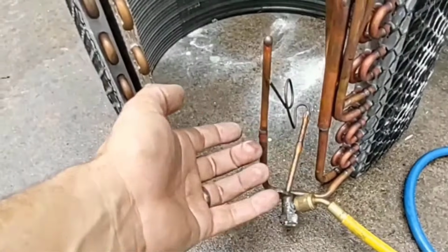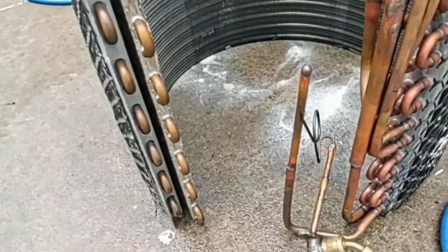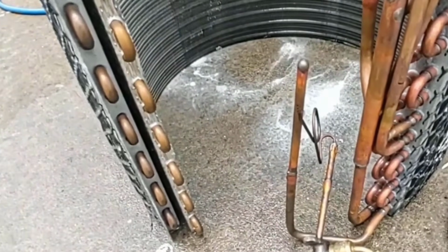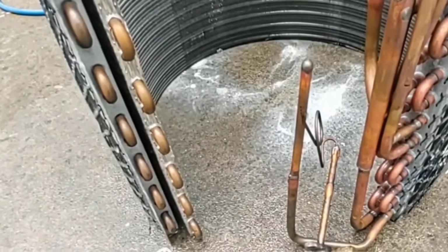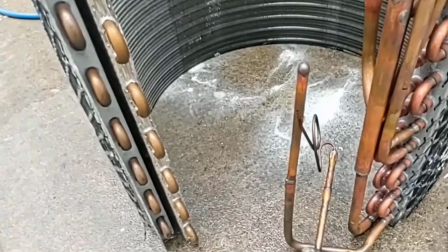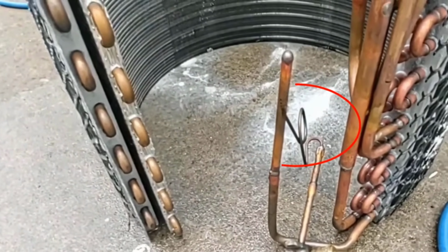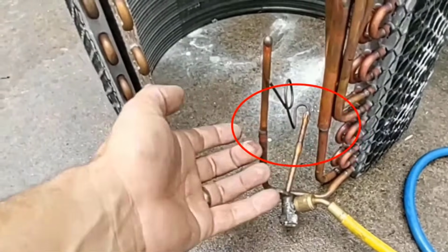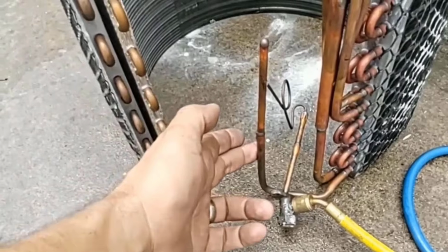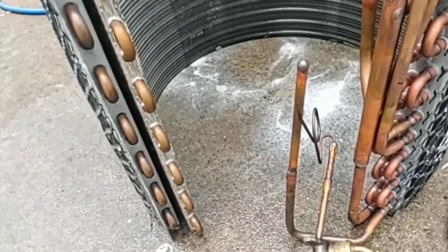When the manual talks about a blockage in the refrigerant tube, it is referring to an obstruction in the system, usually in the condenser capillary. The capillary is a very thin section of piping, essential for the proper functioning of the equipment. It is common for this section to become obstructed, causing the error. The other pipes, because they have larger diameters, are unlikely to become clogged. So it is important to check the entire fluid flow, but the main suspect is the capillary.